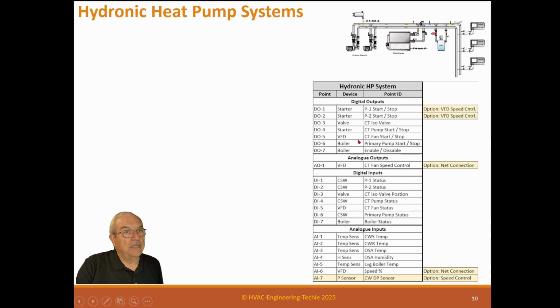So you can see the point list is longer. We have more points for this. Now, the heat pumps are a fairly efficient system, hydronic heat pumps. What makes them efficient is one can be in cooling and one can be in heating, and they can actually trade that temperature back and forth, so they don't need to go through and make temperature here or make temperature here, because this may be acting like a boiler. If it's in cooling, it'll be adding heat. If this is in heating mode, it'll try to draw heat out of the pipe, and that transfer of heat between the units is what makes them efficient. So you don't need to make it every time. You can get it.